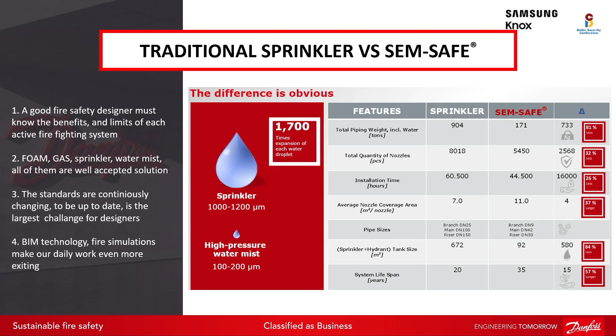The people installing it, with the light small pipes, do it faster simply. Not just the installation cost will be lower, but the time too, because instead of 8,000 nozzles, you only need 5,400 nozzles, because we can have bigger spacing between our nozzles. So it's not a question of one nozzle being more expensive or cheaper - we have to take a comprehensive overview of the project, and this is a nice extract for understanding the main parameters.